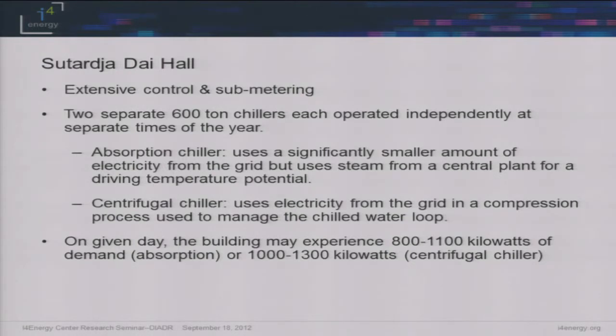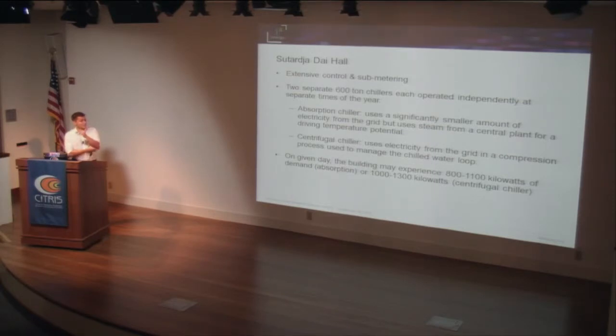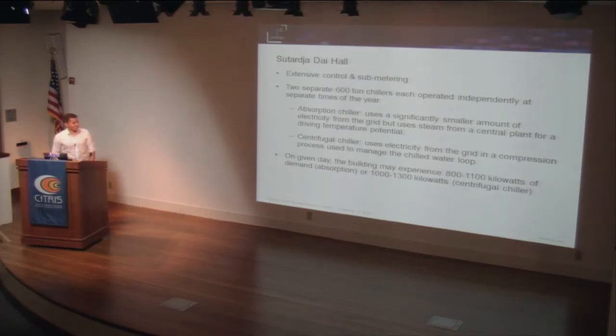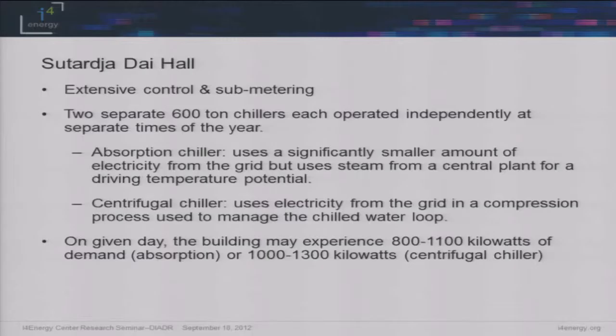Sutardja Dai Hall — obviously the hall we're standing in — has two 600-ton chillers that we're actually working with, which makes for an interesting situation where the building can actually be treated similar to two buildings. Basically half the year we have an absorption chiller running, and the other half we have the centrifugal chiller, which adds an entirely different load because you have all that compressor. So it shifts our baseline about 200 to 300 kilowatts, which is something interesting to account for.